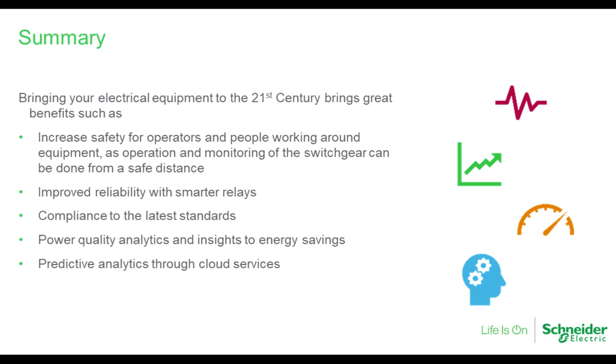So kind of in summary on this, when we look at the entire system, we can bring the electrical system up to the 21st century without replacing all the equipment. We can add new breakers. We can add new relaying. We can add new power monitoring. Now we can add thermal sensors and humidity sensors within the equipment to look at all aspects of the equipment so that we can get increased safety for operators and people working around the equipment, as operation and monitoring of the switchgear can be done from a safe distance.